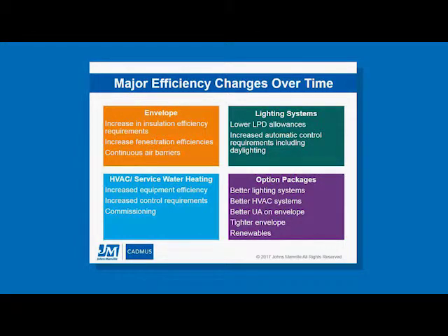And then something unique to the International Energy Conservation Code: option packages. This is to give you a little bit more efficiency after you comply with the prescriptive requirements. So you have several different options. For example, putting in a better lighting system with a lower lighting power allowance, or a better mechanical system with increased efficiency HVAC systems, a better thermal envelope, actually increasing the insulation levels and putting in better windows, so a better UA on the envelope, and also a tighter envelope because they're finding significant energy savings if you tighten up the building shell, and that gets back to our continuous air barrier requirements. And then the ability to put in renewables to offset the energy use of the building. So these are some of the major changes that we've seen over the last number of years from an IECC standpoint.